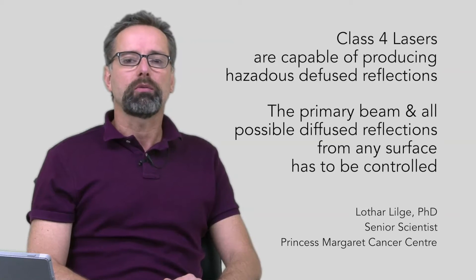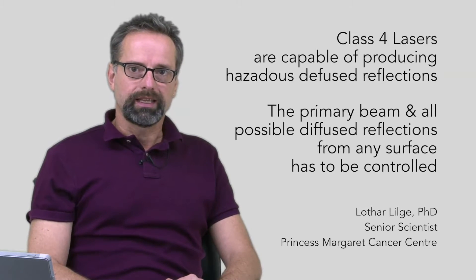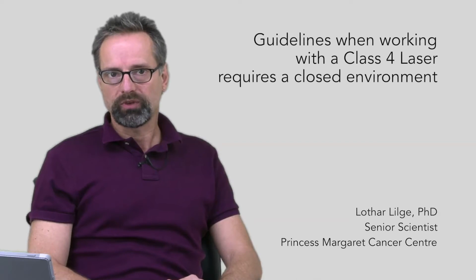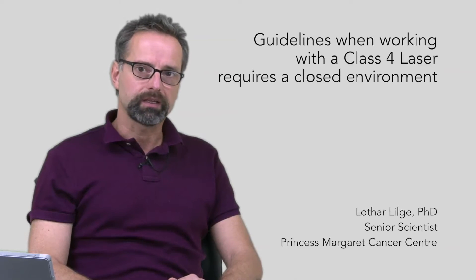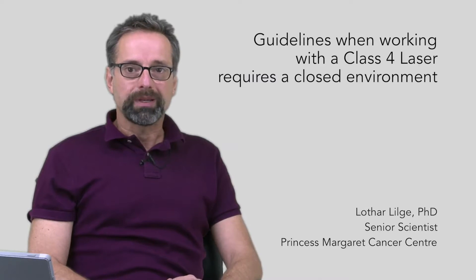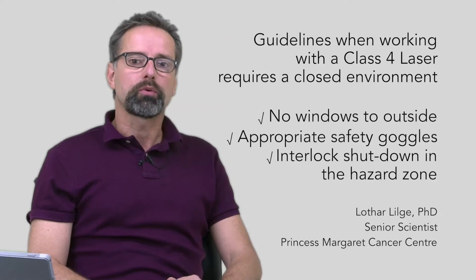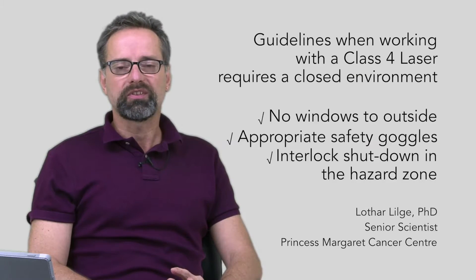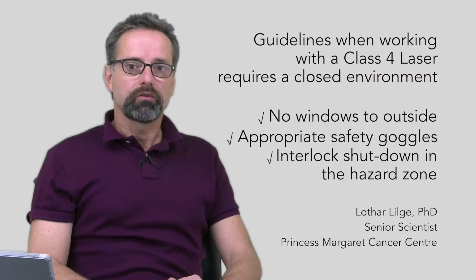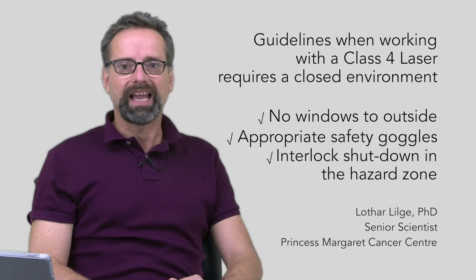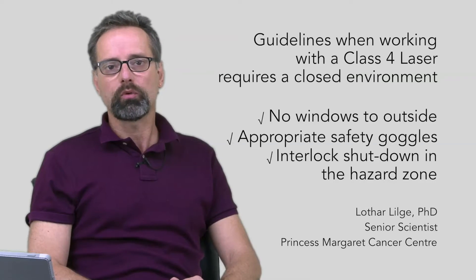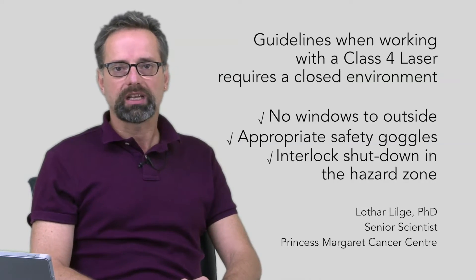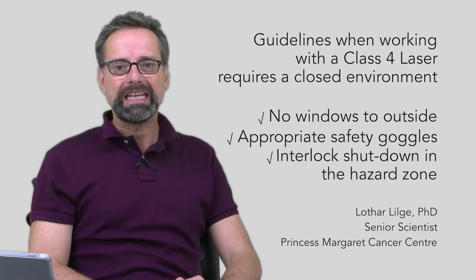The guidelines require that you are working in an enclosed environment with no windows to the outside or other parts of the building, that all people inside that room wear appropriate laser safety goggles, and it goes even so far as to state that if the door is open, the hazard zone control is broken and the laser has to be shut down automatically — so there must be an interlock between the door and the laser itself.